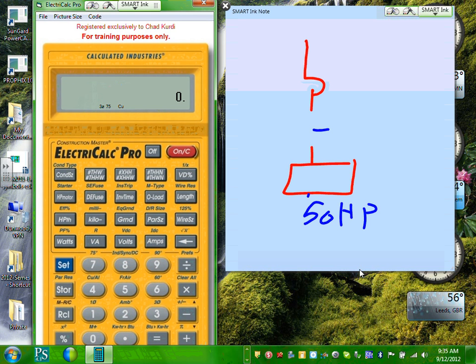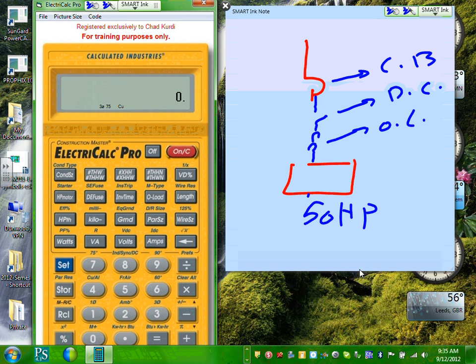For motors we need a circuit breaker, and we need a disconnect. I have a disconnect, and I need an overload. See how? So I have a circuit breaker, I have an overload condition, and I have a disconnect. So this is circuit breaker, this is disconnect, this is overload. Everybody knows that motors have all these systems in them, and this is the conductor. Okay, so let's go size this.